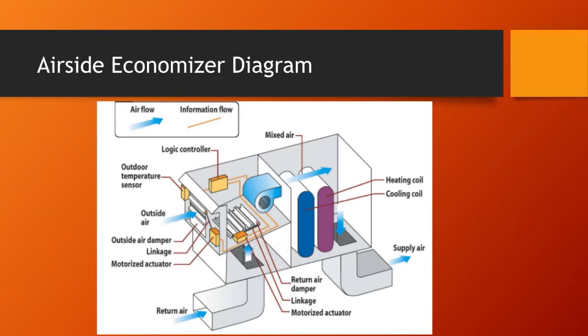Alright, so here we have the air side economizer diagram. This is going to be your rooftop unit mounted up on top of your building. Right here you're going to have fins. Usually there's going to be a rain hood to keep weather out and not have to worry about sucking in water inside your system if it's raining outside. So you're going to have these fins that are controlled by actuators. That's all going to be through your building automation system on how far those dampers are open. That's going to be bringing in outdoor air if the conditions are right.